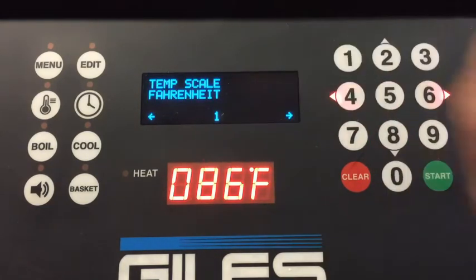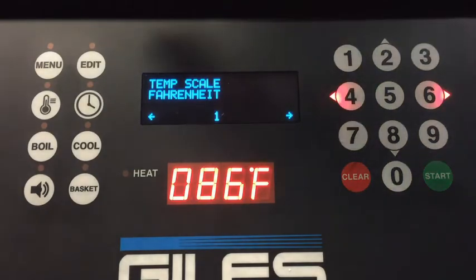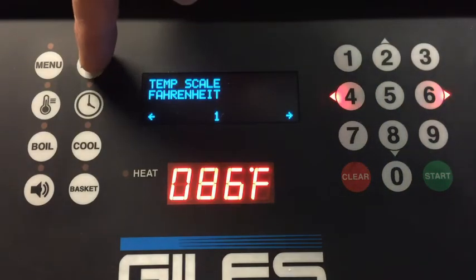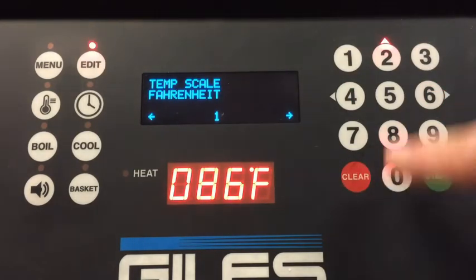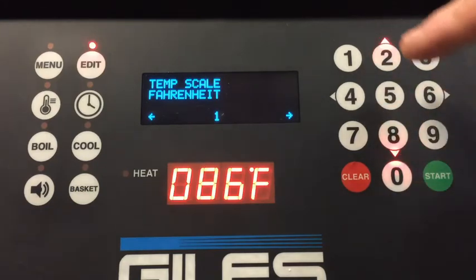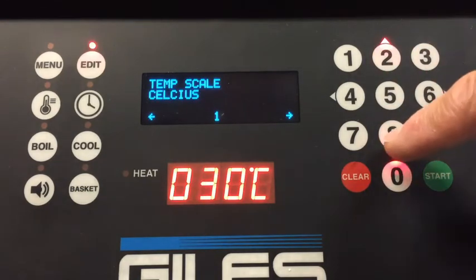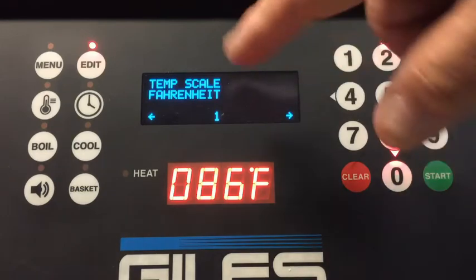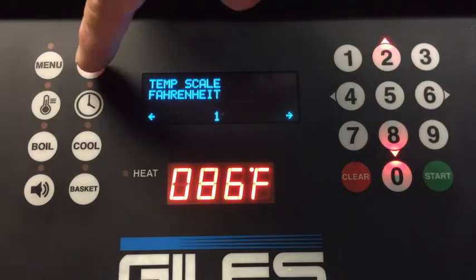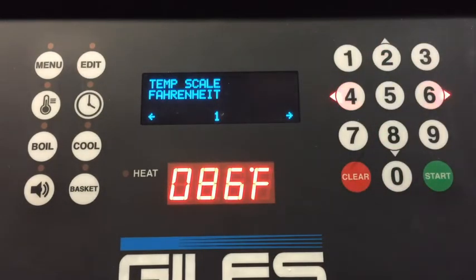This is your steps, number 1. We're going to leave it in Fahrenheit. That's a good place to leave it. Now, if we wanted to change this, at this point we would press the edit key, and then you'll notice we've got the 2 and 8, so we can go up or we can go down. We're going to leave it in Fahrenheit though, so we're going to press edit, and that saved it, and then we can go on to the next setting.